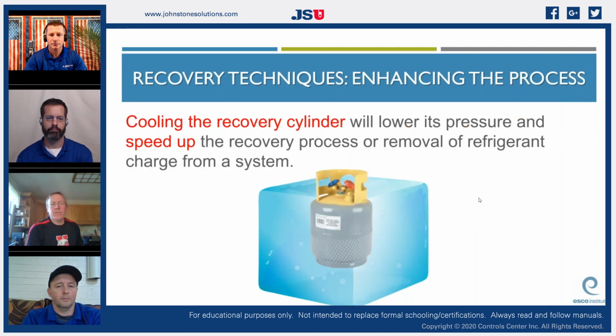So let me back up here. We do this all the time in the field: cooling the recovery cylinder. Not many people have a block of ice to stick it in. But if you've ever been out there on a system and you're recovering, especially if there's quite a bit of refrigerant or non-condensables in it, it's a nightmare. And that tank gets very hot. And as this tank heats up, the pressure rises. And just common basic science here, if the pressure rises, it's harder to put more refrigerant in it. So basically, we usually just took a hose and cooled them down.